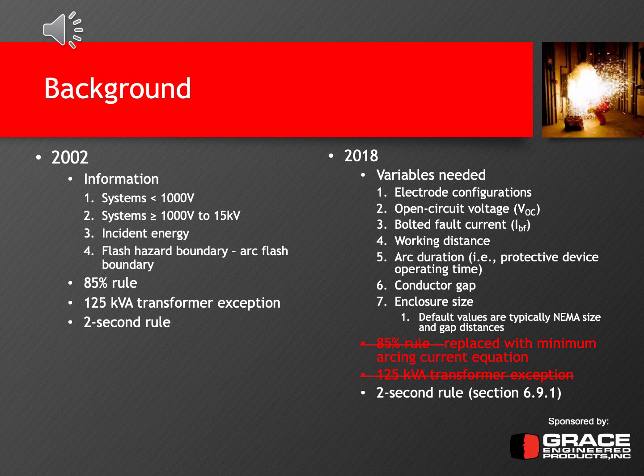You would then calculate the incident energy based on whichever branch you were on, and then you would calculate the arc flash boundary. 2002 also introduced the 85% rule. Well, I believe that was a 2004 amendment that was included in 2002. But the 85% rule basically says once you calculate your arcing current and you have your incident energy and arc flash boundary, you need to recalculate the incident energy and arc flash boundary with an 85% arcing current from what was originally calculated.